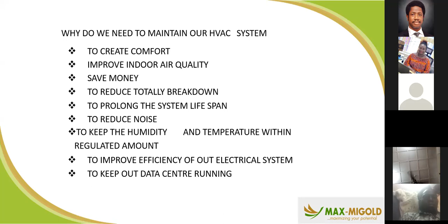Then I will teach you something: there's what we call redundancy in air conditioning systems. When designing for a data center, if you are to give the data center 20 kilowatts of cooling, make your design 30 kilowatts. There should be equipment on reserve in your facility, so that if one unit breaks down, you can activate the other one while you fix the problem. Your data center must continue running at the temperature it's set to.